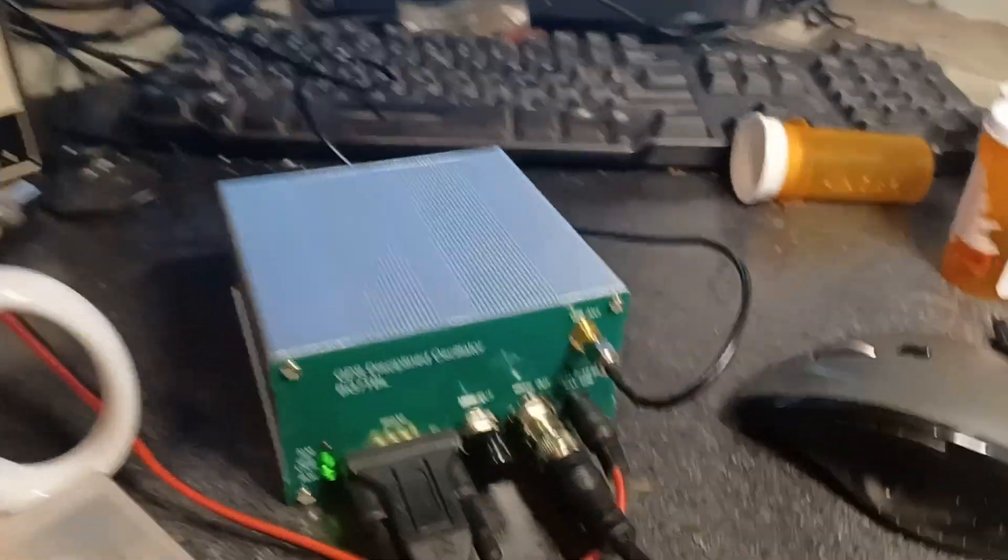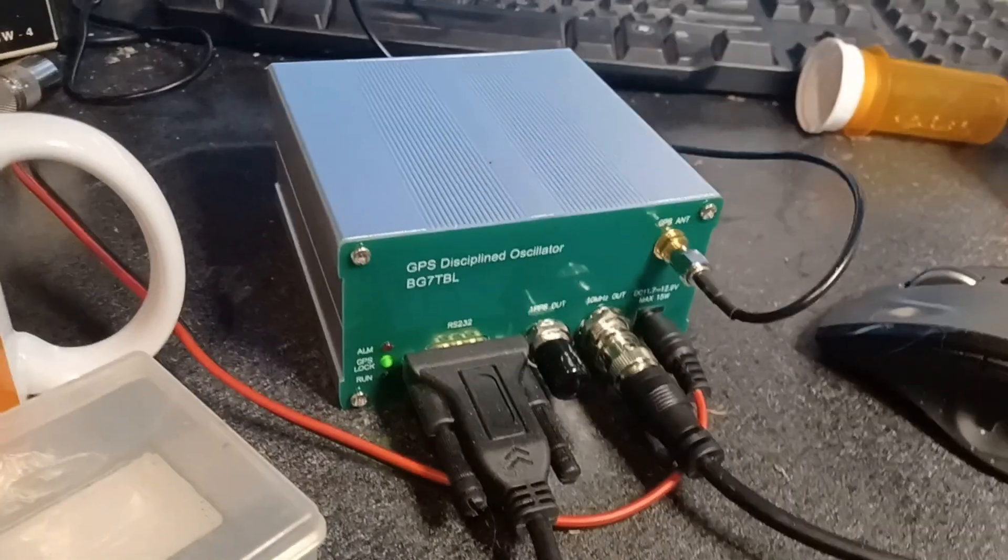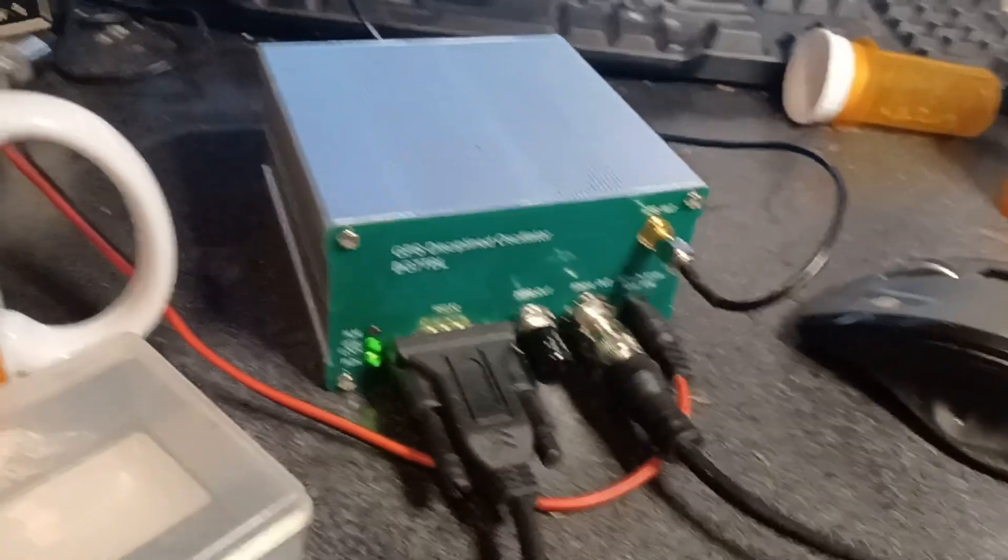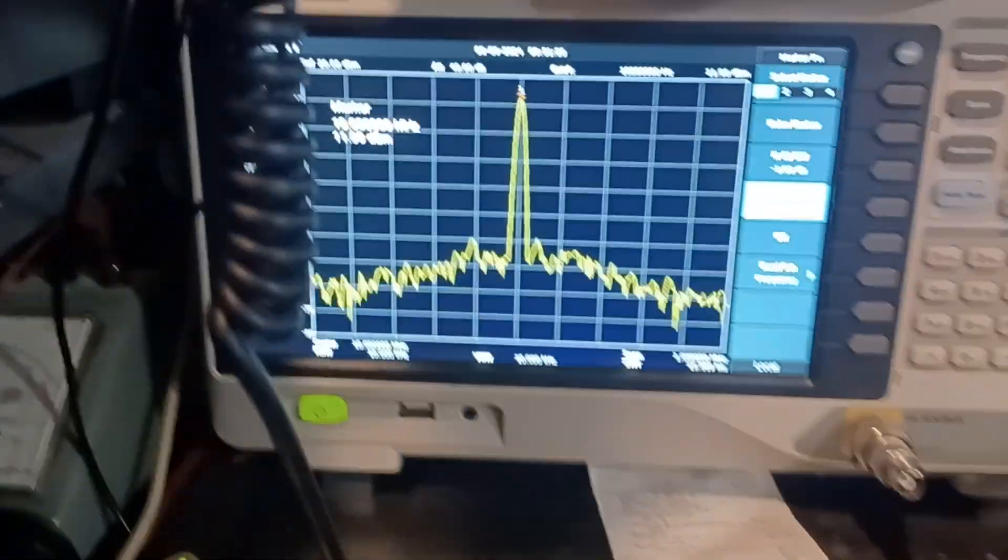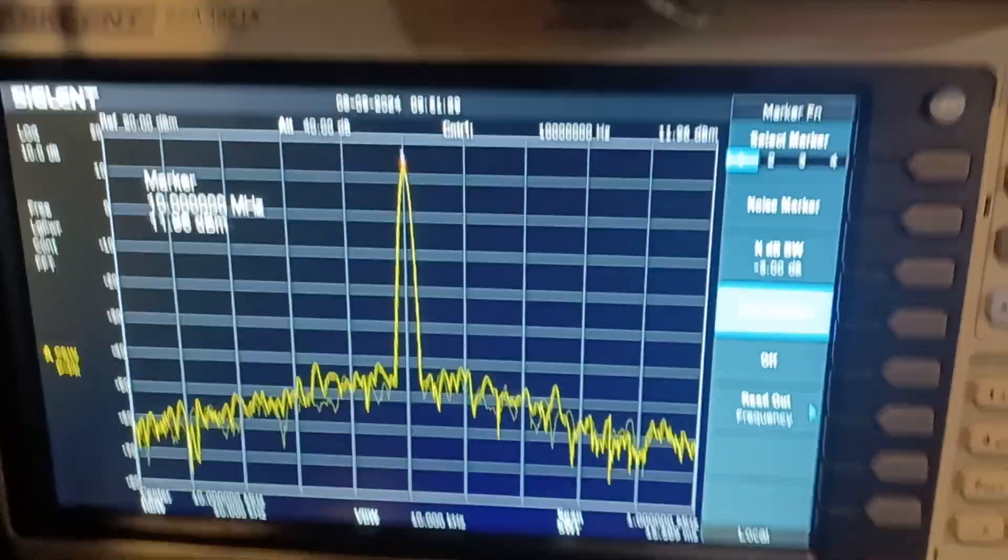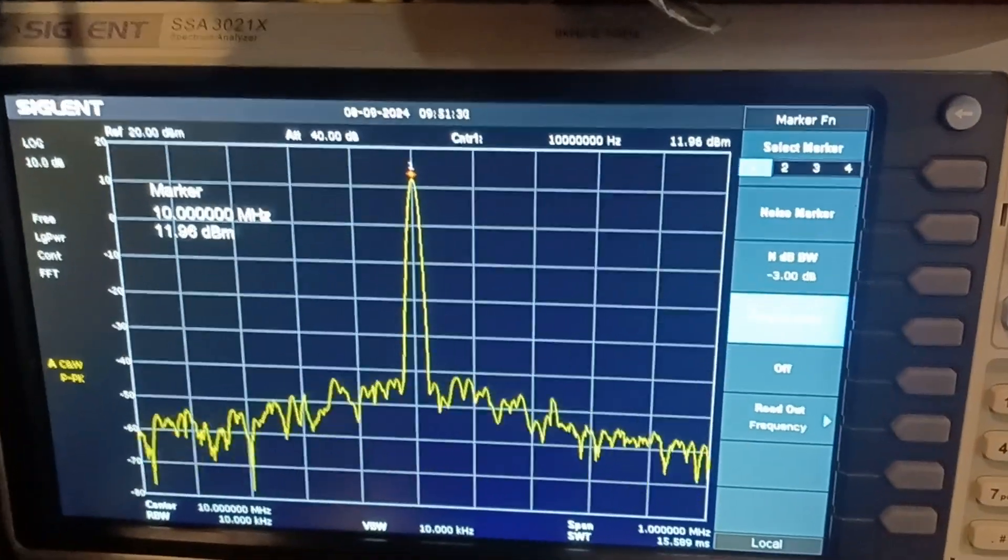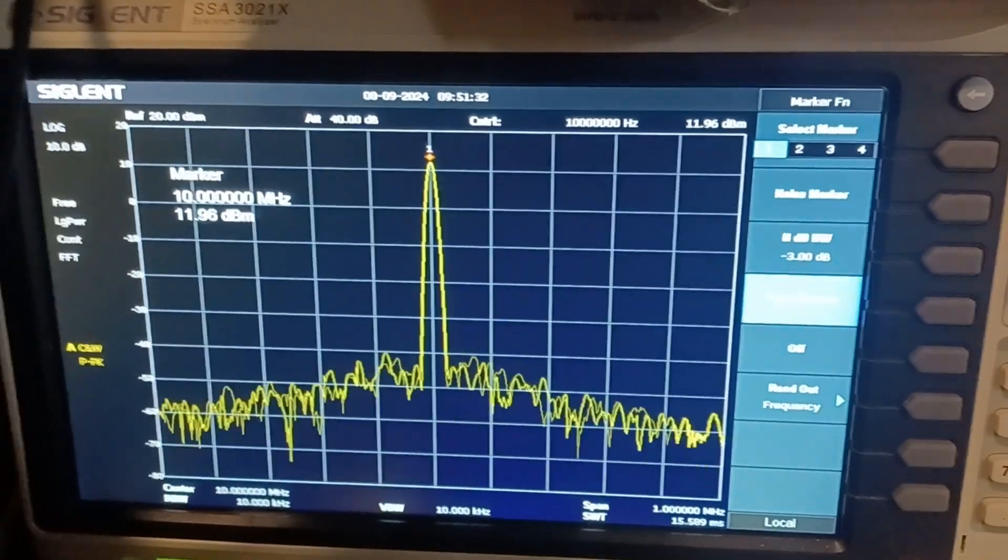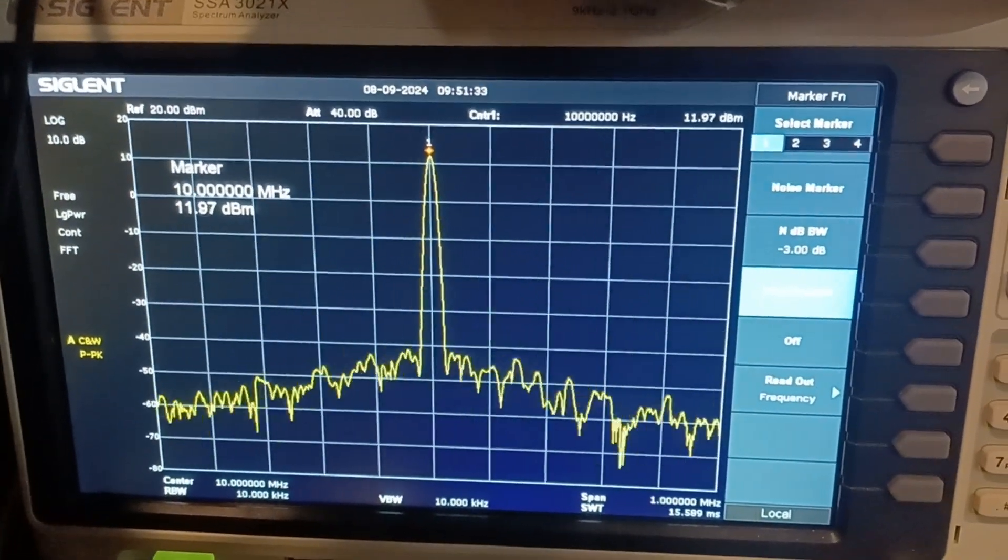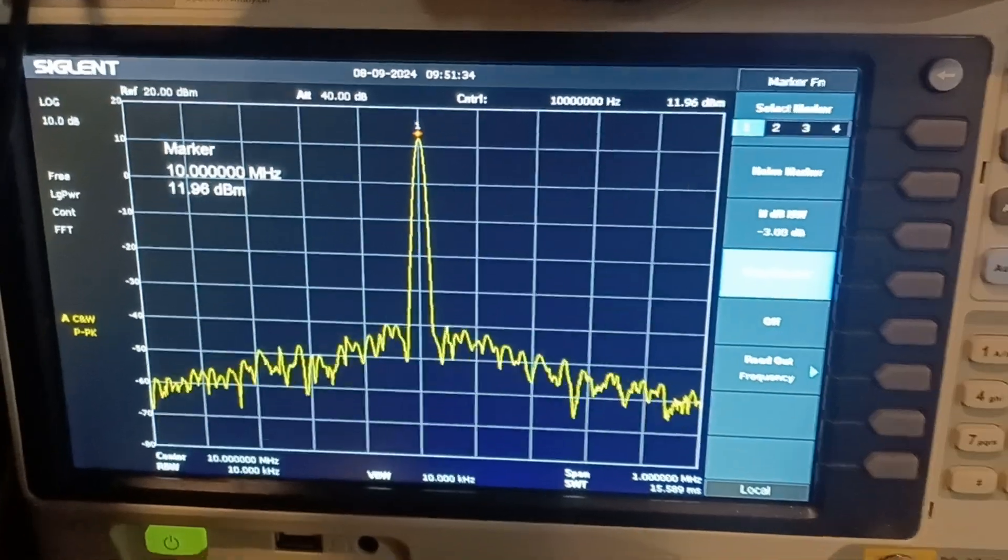Alright, now let's disconnect the GPS-DO from the oscilloscope, plug it into the spectrum analyzer. And right there it is at 10 MHz and a good solid signal.